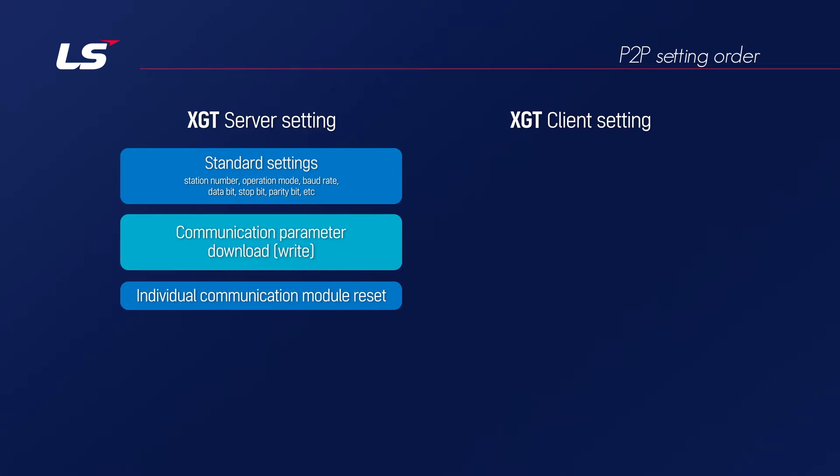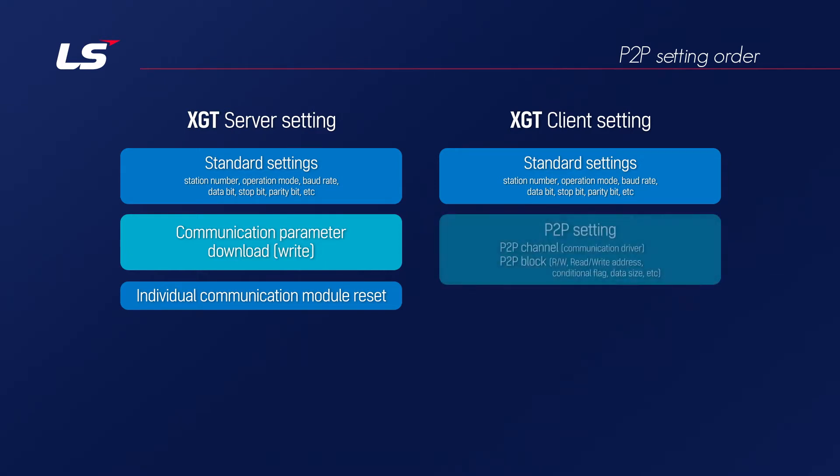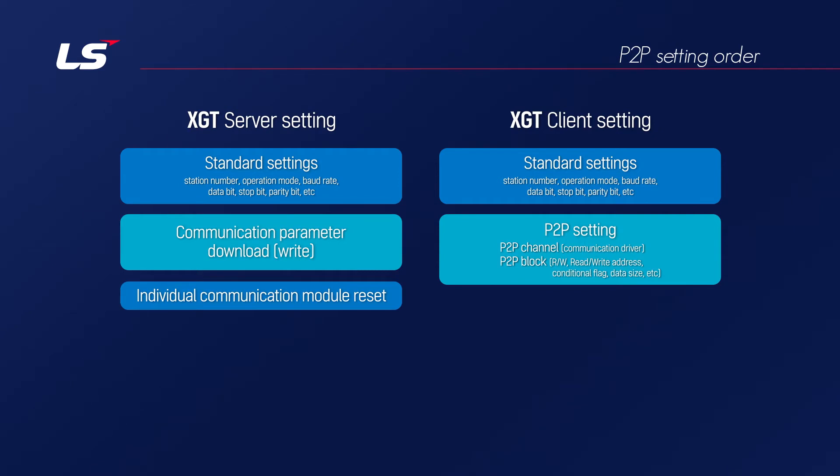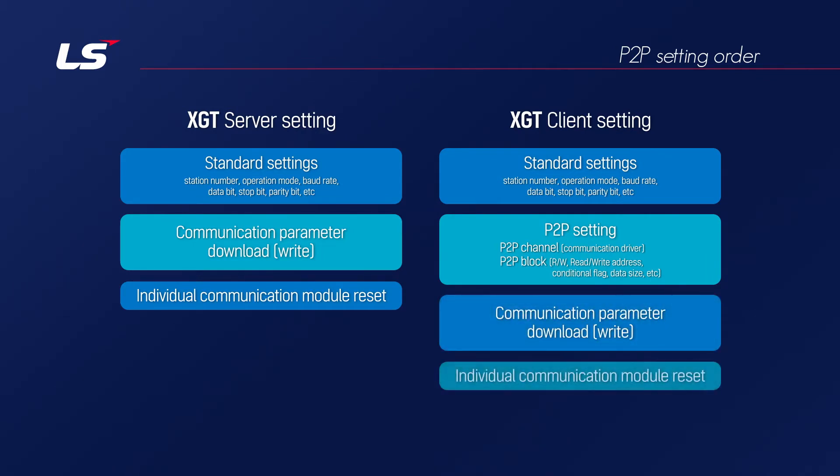Let's look at the setting procedure of the master using the XGT client. First of all, it is the same as the previous XGT server setting. As P2P communication method is used, add P2P to the module. When P2P is added, P2P channels and P2P blocks are created, set in the order of channel and block. After setting communication driver setting in P2P channel, user sets the message to be sent to the server in the P2P block setting. When the setting is completed, download that to PLC, and the module needs to be reset to apply the changes.